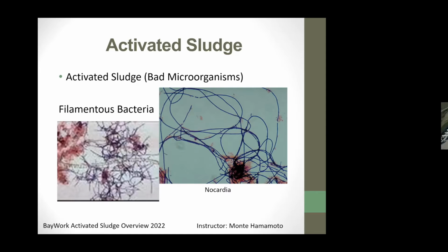If you're longer in your MCRT and you see these guys show up and you have some serious problems, some of the guys who have been in the industry a long time refer to it as "roast them and toss them." You hit it hard. I mean, you're looking at 50, 100 ppm. Wow. Okay. Very short period of time. Mm-hmm. And then you're wasting like crazy to get it out of your system and then watching things closely. You hit it really hard, short period of time, get rid of it, and then slowly bring your activated sludge back up. So again, it all depends on where you're at on that spectrum. Okay. All right. That's helpful. Thank you. Mm-hmm.